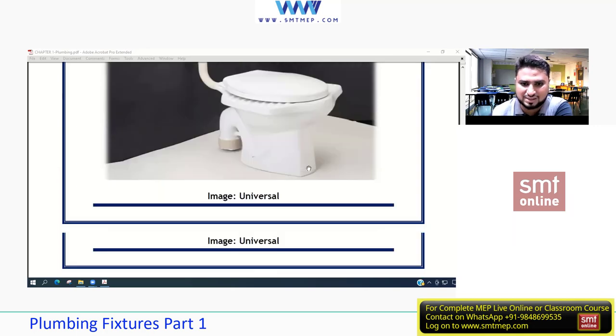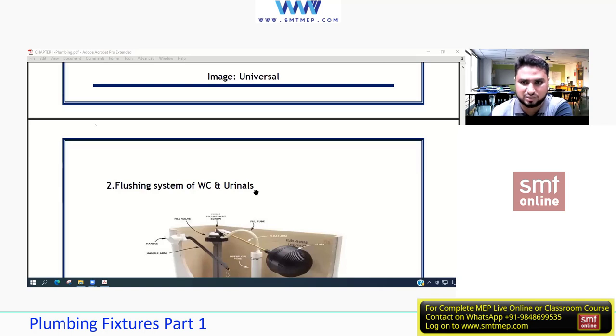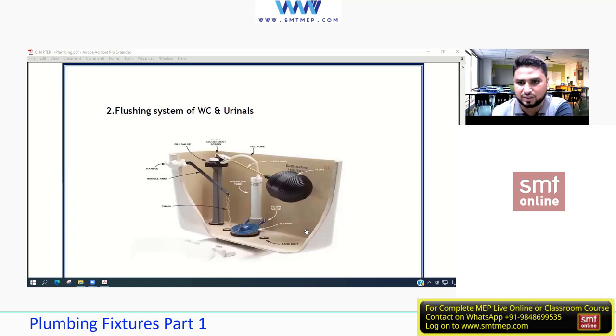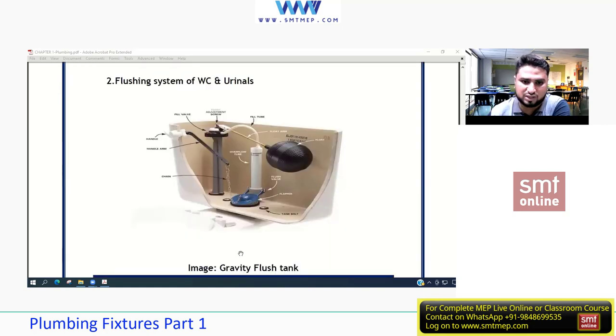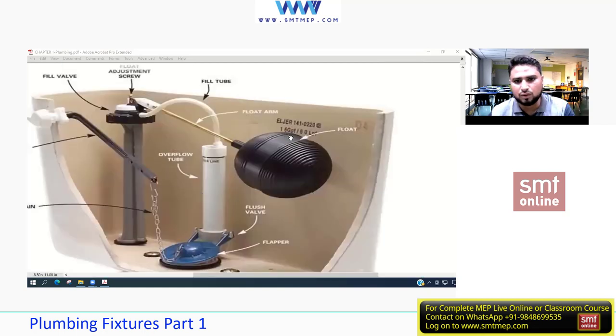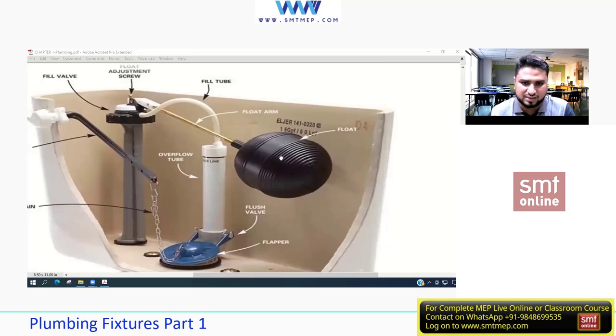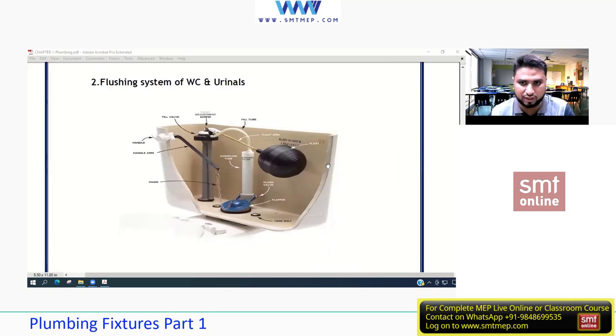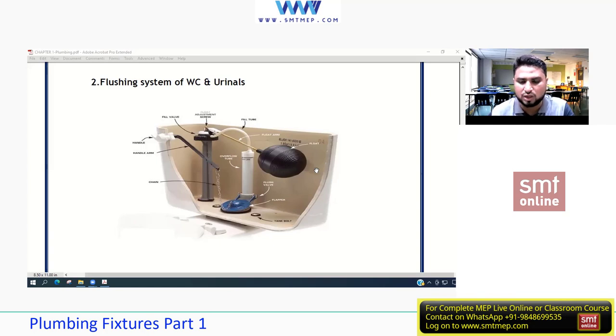Now the flushing system for WCs and urinals. This is a gravity flush tank — it works by means of gravity. As per IPC standards, it delivers 1.6 GPF (gallons per flush). It holds 1.6 gallons of water and drains that in one flush. Hard water is recommended for flushing; soft water is reserved for drinking and cooking.